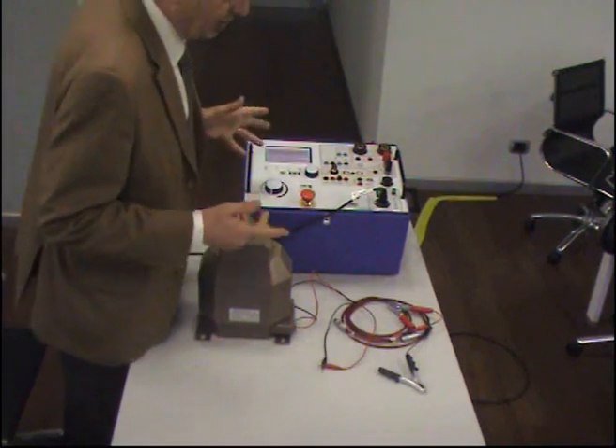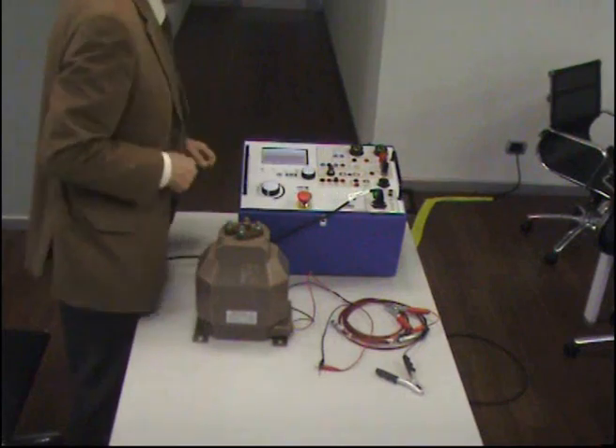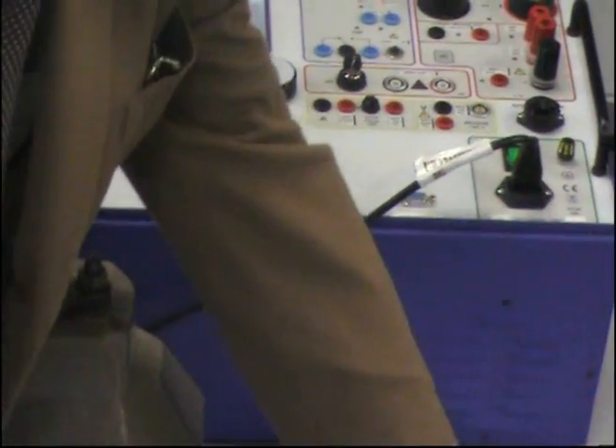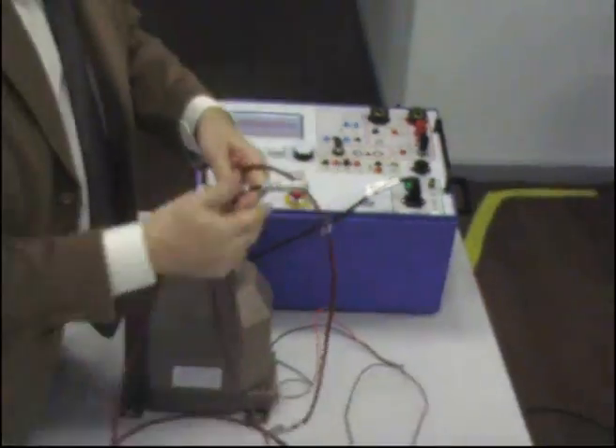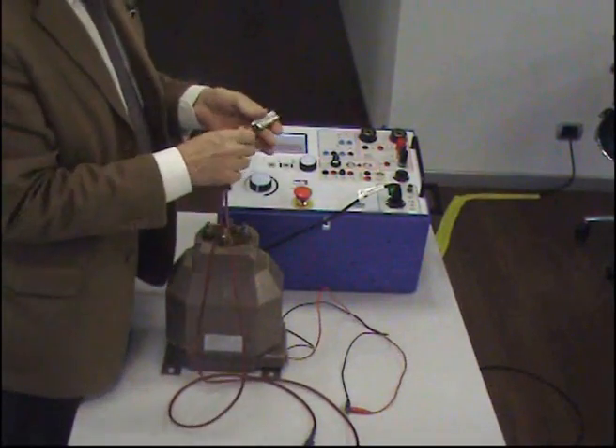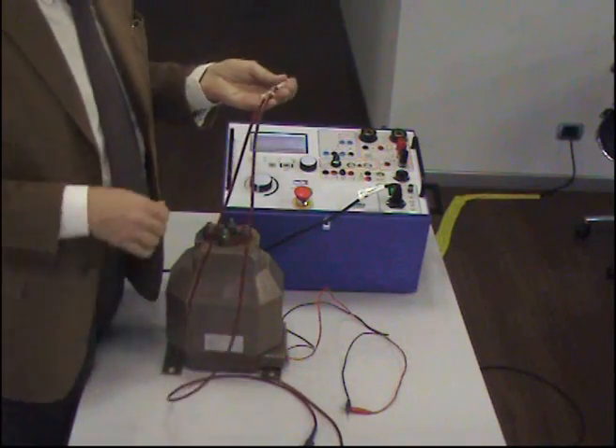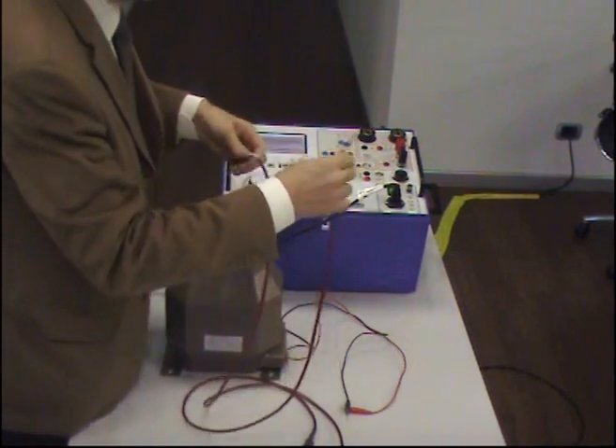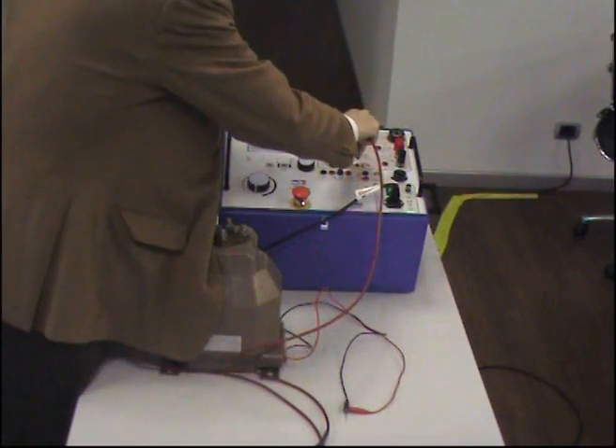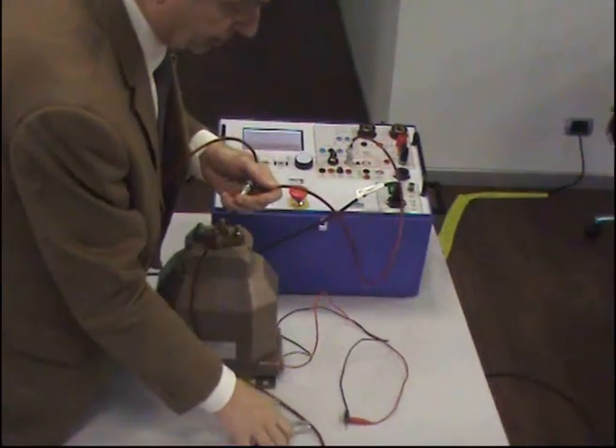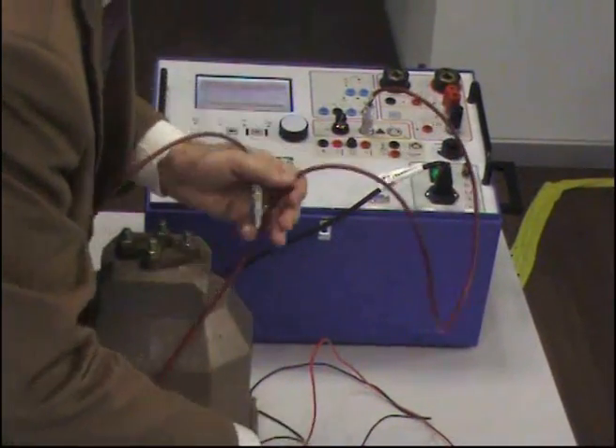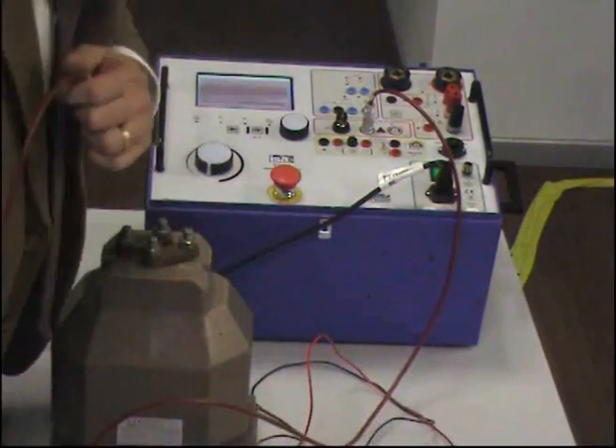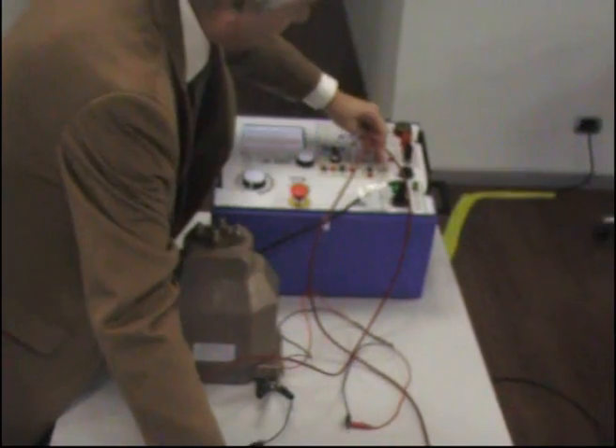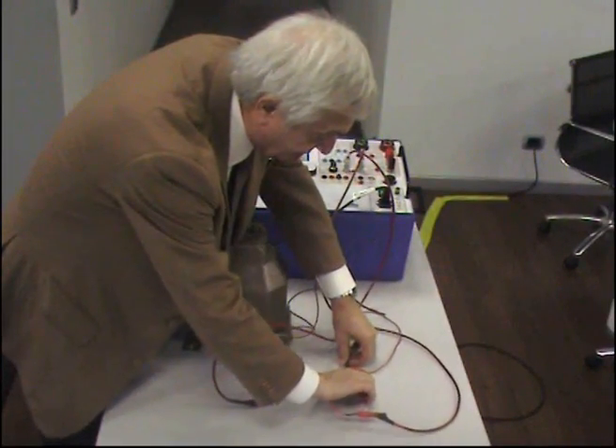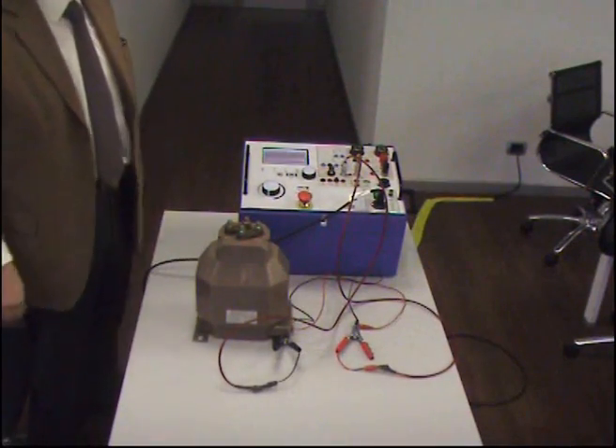How to perform the test? I need to use the high voltage generator, and the connection to the high voltage generator is performed by these two high voltage cables. These are laboratory cables, as are the other ones. So actually, in your case, you will receive much longer cables. So I connect one of them here, and for instance, this one is the, no, sorry, this is the black, and the other one, that is the red, I connect it to the secondary of the current transformer, okay?